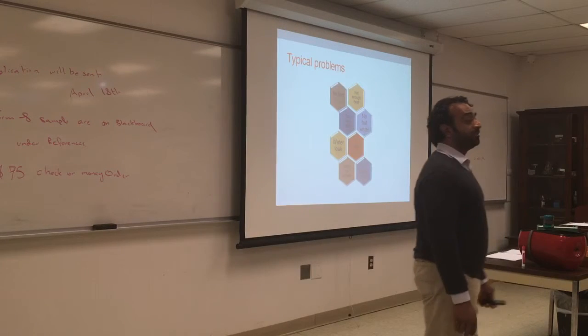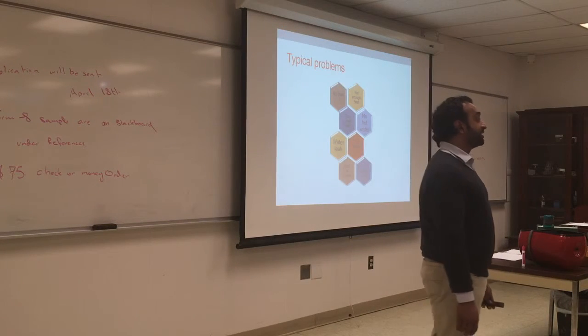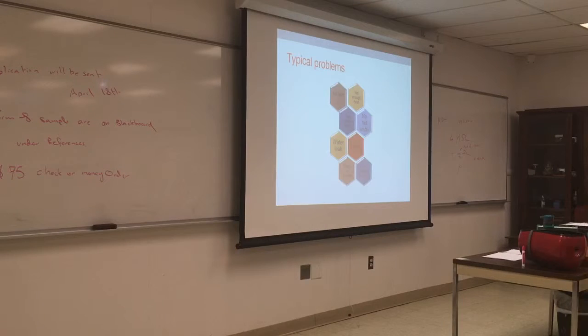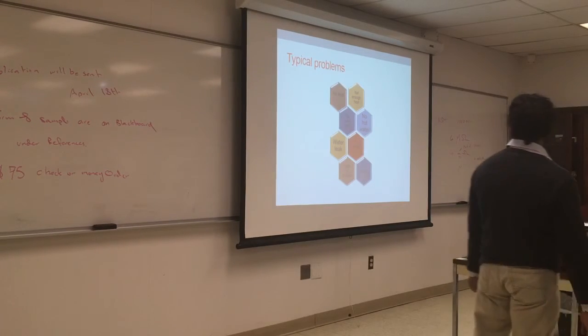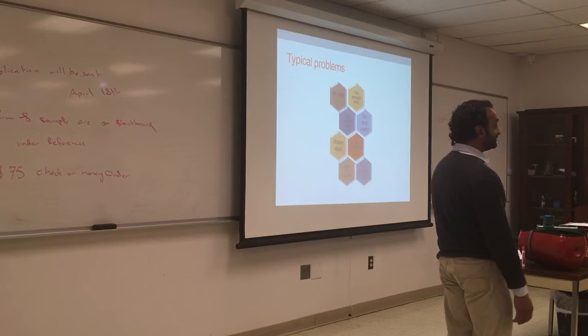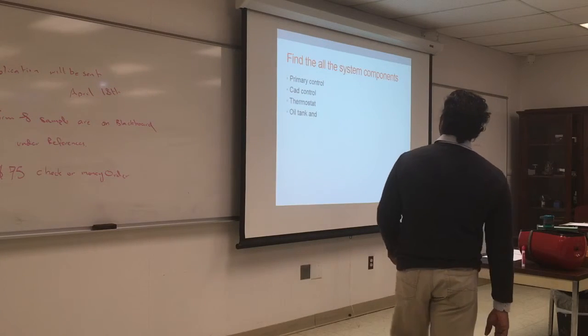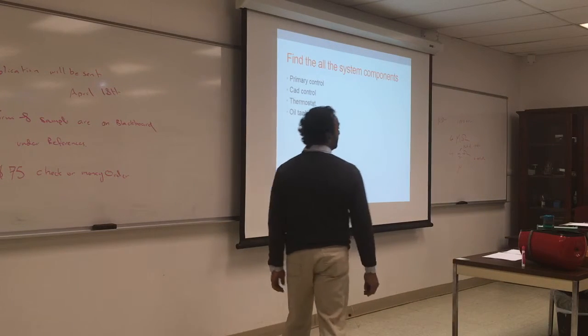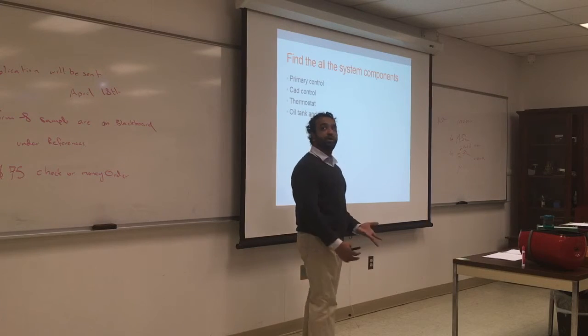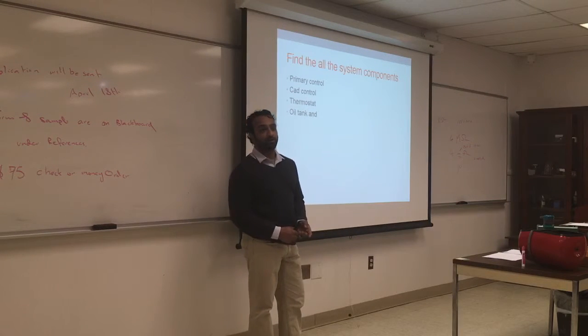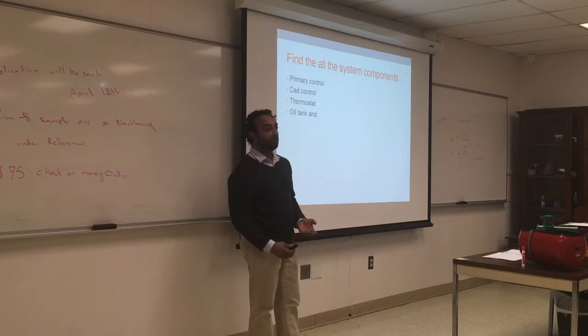Also, the location of the thermostat. People don't understand how it works, so you'll see maybe a lamp or light fixture next to it, or they put a fan facing the thermostat, or an AC close to the thermostat, so you've got to look at these things a little bit. A candle, that's possible. Find all the system components, that's very important. Before you start, I said the first 45 minutes, you want to go and investigate and find all the components. Make sure we have all we need.